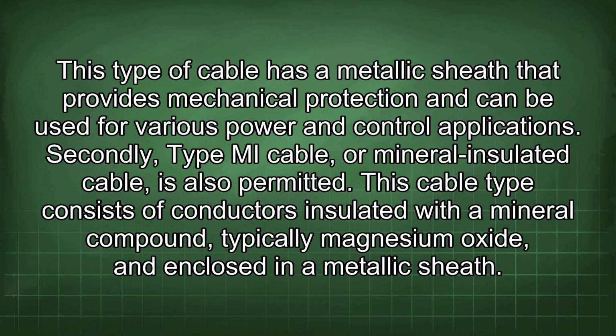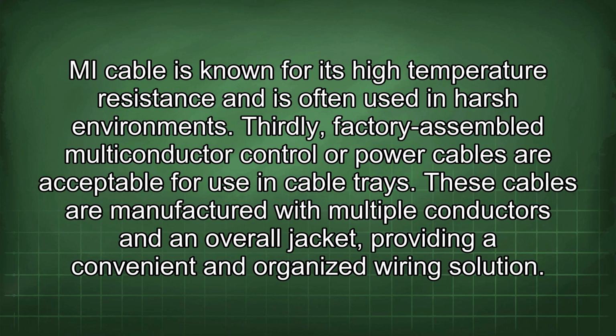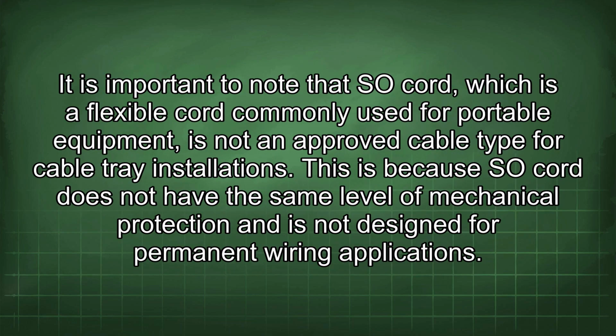This cable type consists of conductors insulated with a mineral compound, typically magnesium oxide, and enclosed in a metallic sheath. MI cable is known for its high temperature resistance and is often used in harsh environments. Thirdly, factory-assembled multi-conductor control or power cables are acceptable for use in cable trays. These cables are manufactured with multiple conductors and an overall jacket, providing a convenient and organized wiring solution. It is important to note that SO cord, which is a flexible cord commonly used for portable equipment, is not an approved cable type for cable tray installations.